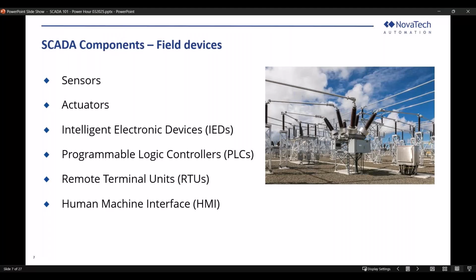What confused me previously is sometimes people call the whole cabinet the RTU, and terminology-wise people do it all the time, and it's fine, but I just wanted to clarify because I got confused. Really, an RTU cabinet is the cabinet that has the RTU device in it, but the cabinet itself should not be called an RTU, it should be called an RTU cabinet. The RTU cabinet usually contains an RTU device. For example, NovaTech's Orion is an RTU device, and in that cabinet there's usually your switch, your routers, your terminal blocks, your I/O modules, your touch screen for your HMI, and so on, and that makes up the whole cabinet. But I just want to clarify, the device itself is the RTU, the remote terminal unit itself.